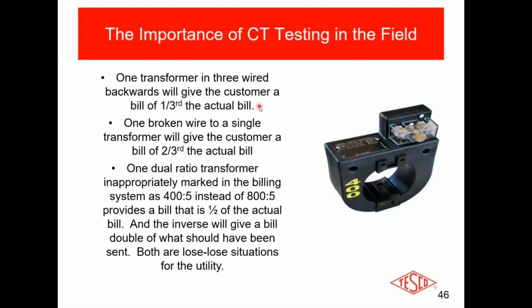All right, one broken wire to a single transformer, one broken wire. You're losing 1/3 of your bill. Now, do most wires break clean? No, they don't. A lot of people are using stranded wires. It's the most popular wire rather than the solid copper wire. Stranded wires, you start losing more and more strands in there. And even after the wire breaks, the wire is making contact, not making contact, making contact, not making contact. Do you actually lose a full 1/3 of the bill? No, you may not lose a full 1/3 of the bill, but you may lose a good part of that 1/3.